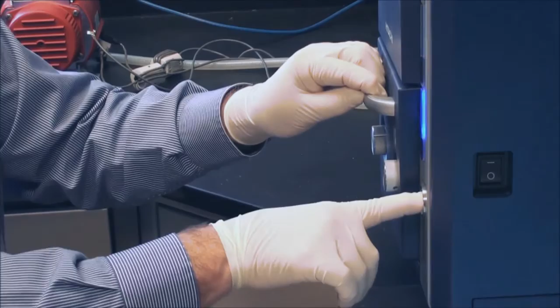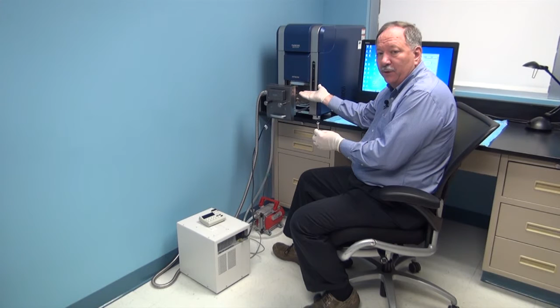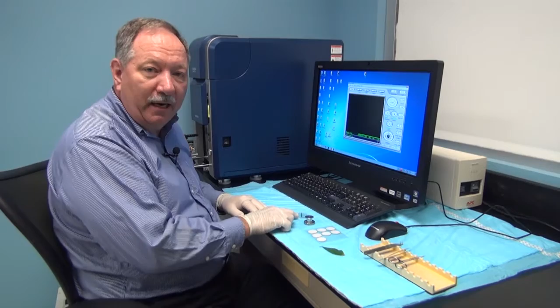If you find that using the standard method your samples shrivel, you can always use a cold stage, which will drop the temperature of your sample inside the microscope to -25 degrees Celsius. At that temperature, your samples will shrivel much slower, which will extend the period of time you can use for observing your samples. You need a double sticky tab, which will attach to our sample stub, which is 25 millimeters in diameter. You need an adapter and an Allen wrench.